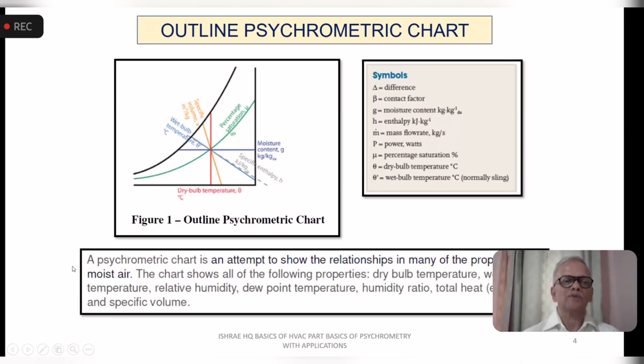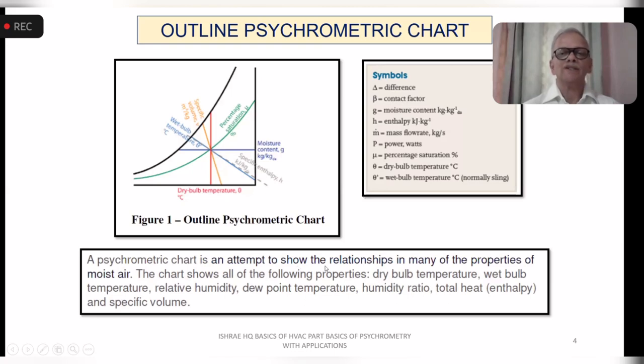Now, the description here is that the psychrometric chart is an attempt to show the relationships in many of the properties of moist air. The chart shows all of the following properties, namely dry bulb temperature, which is this vertical line, wet bulb temperature, which is this blue line, relative humidity, which is that curve, dew point temperature here, saturation line, humidity ratio, which is here, moisture content, and total heat or enthalpy, and the specific volume, which is this line.